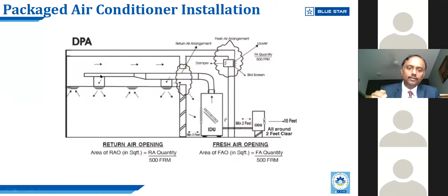Kumaresh, can you just show the tail end of the ducting? Towards the end, the air will not reach. When that air is not reaching, people in the farthest end of the place will not get cooling. In some offices, you'll see zones with hot spots and zones with cold spots. The reason is the duct design is not done properly — because there's pressure to maintain higher false ceiling heights, and because of that the aspect ratio is compromised. 1:4 is not maintained, and hence you get this problem. So when you design false ceiling heights, please take the height of the ducting into account too. This is a very important tip I'd request all of you to keep in mind.